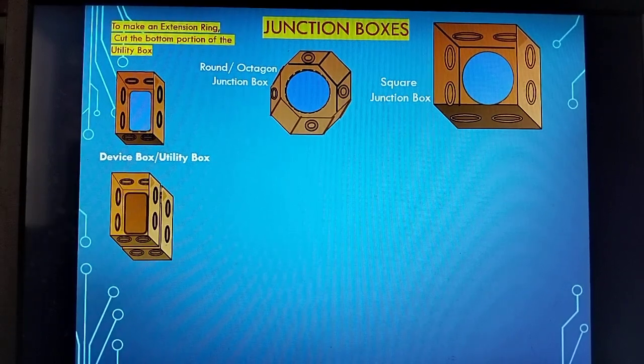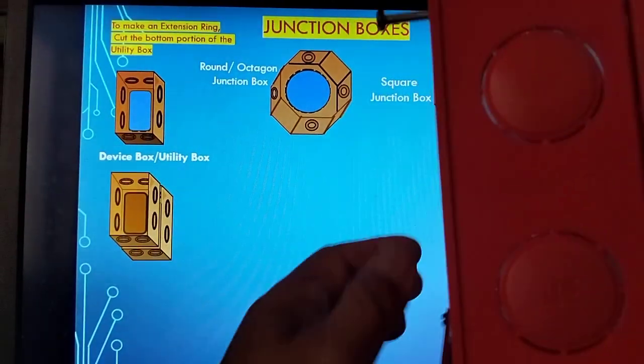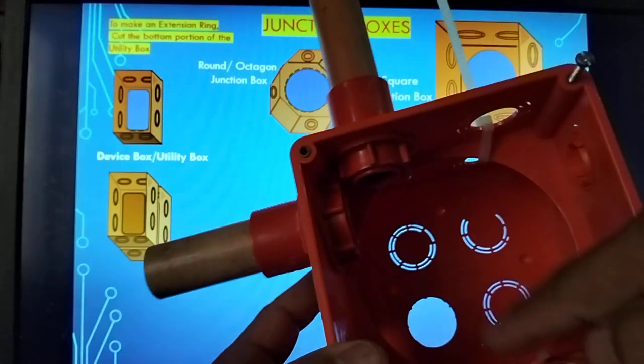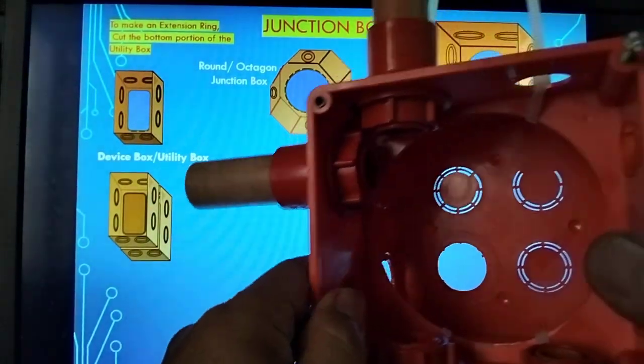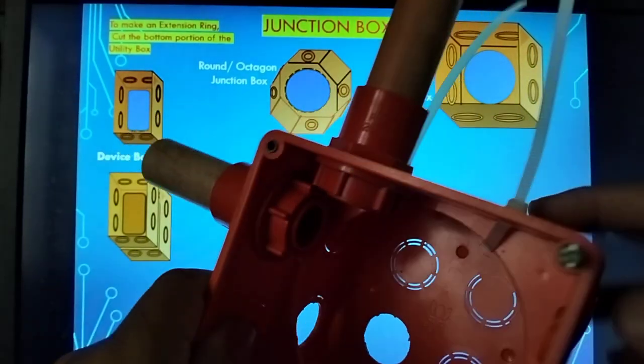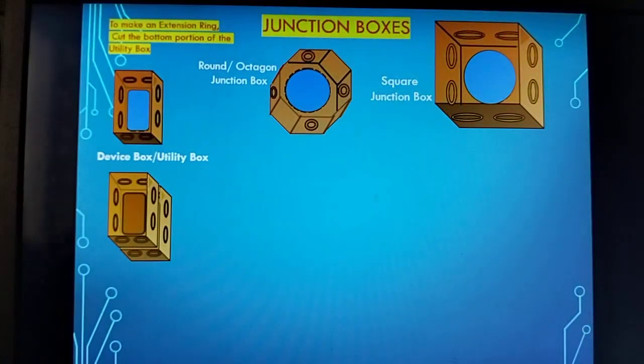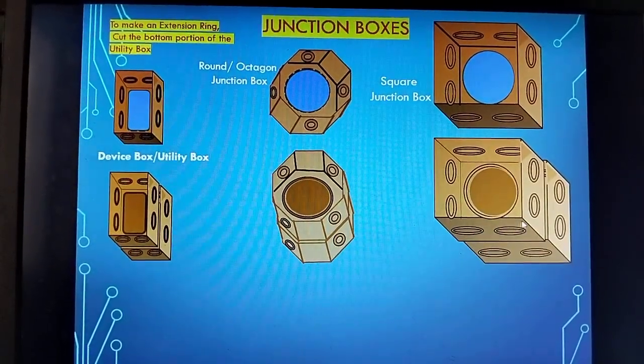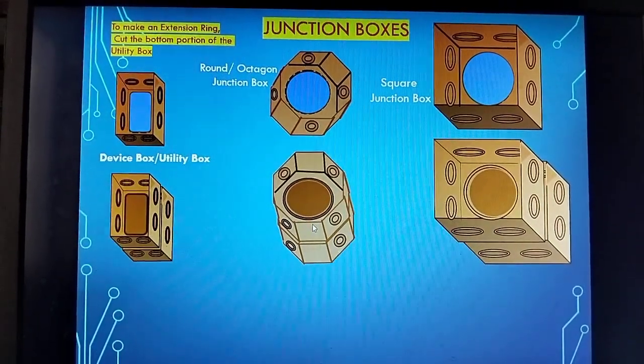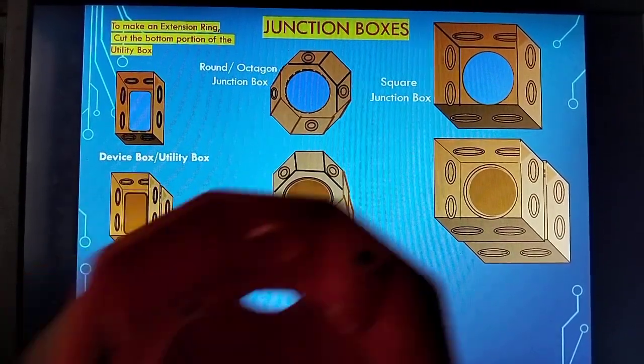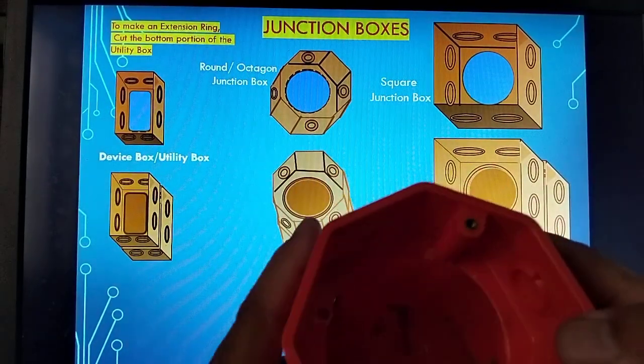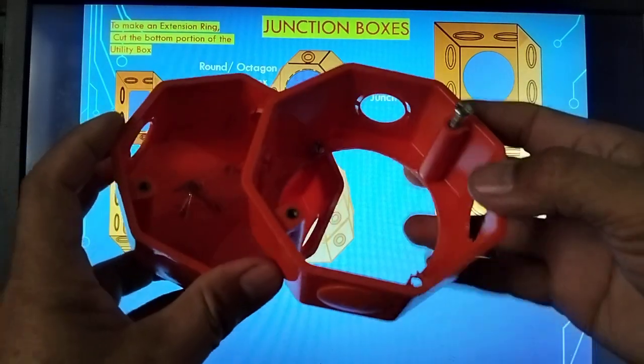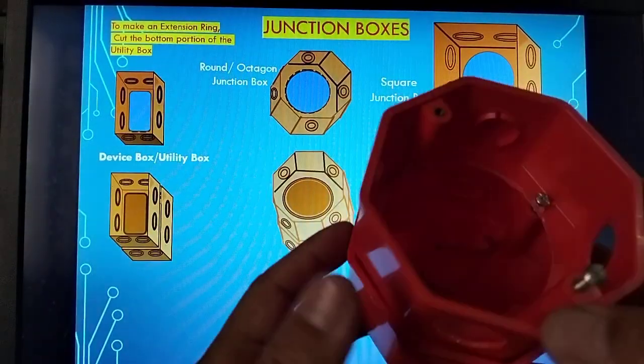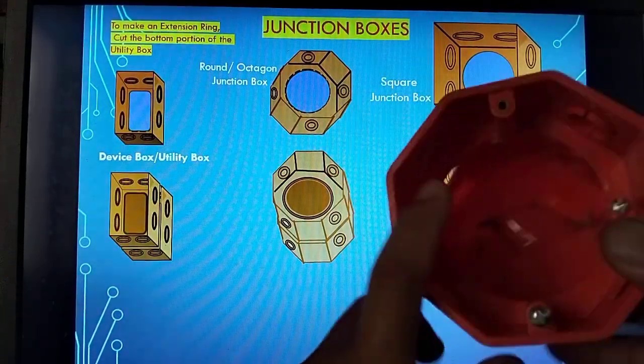I'll show you in actual like this, no? See, this one. You just make use of the hole saw and then use the pipe connector, pipe fittings or bushing. Then if you don't have a screw or bolts, use the cable tie. This one, no? For the square box. Now let's say your junction box is not enough, you make it like this. Okay, you just use a screw, see, use the hole saw, then put it on top of another junction box or round box, then put a screw here, like this one.